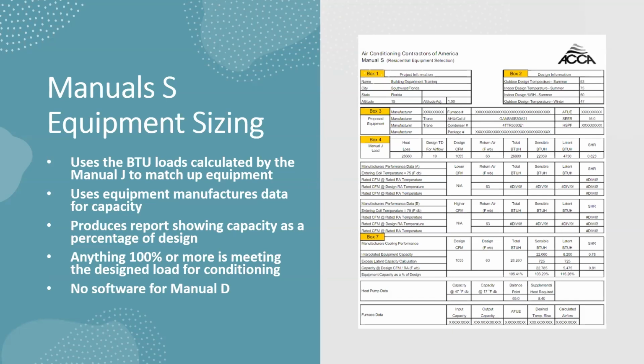It's going to have to be as close as you can get it, and being slightly over isn't a big problem. But my big takeaway from that is, A, the project information needs to match the Manual J. The design locations or the design temperatures should match what's code required. And then all the way at the bottom, you're going to say, what is the capacity as percent of design? It needs to be as close to 100% as possible.